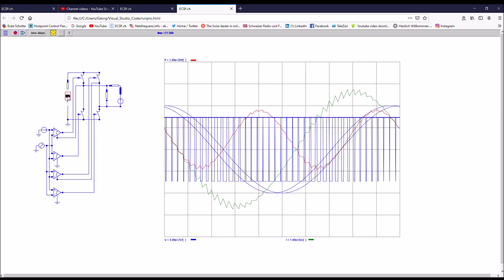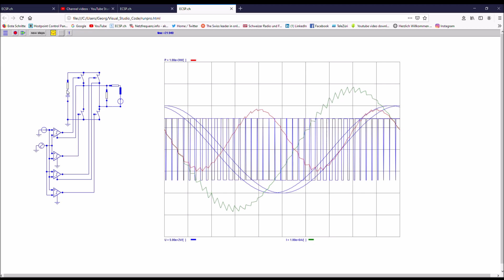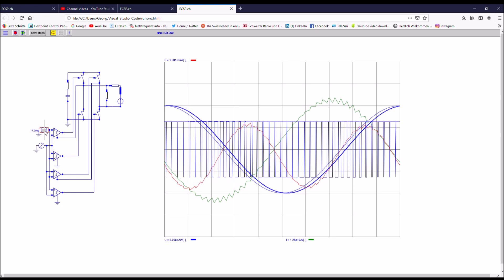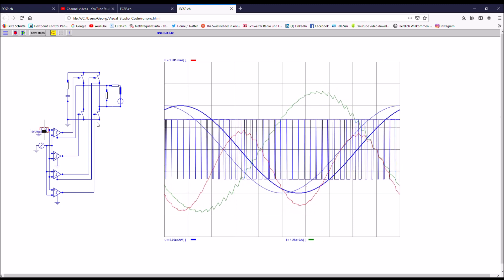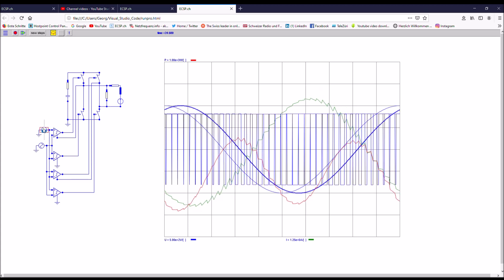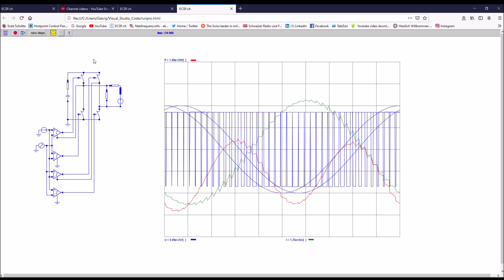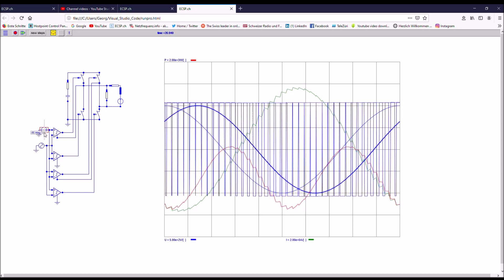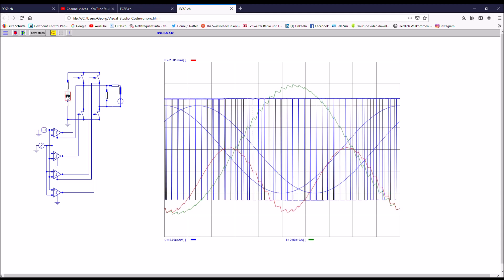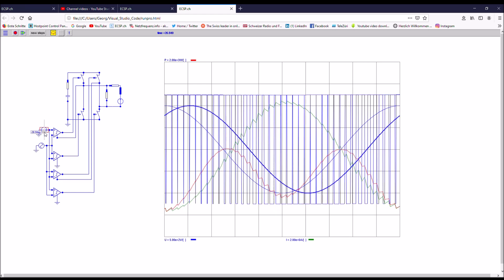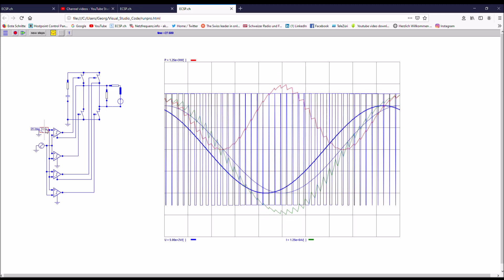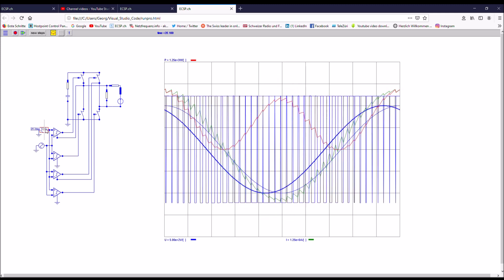You can see the converter output is now lagging — the load is leading the converter — and the voltage at the capacitor is decreasing. That means power flows from the DC side to the load side, causing the DC voltage to decrease. The other way around, when I move to a leading converter angle, the load side is leading the converter and power is now fed from the load side back to the DC side. This is how I control the power flow — with a leading load you can see the capacitor voltage increasing, and with the converter leading, the DC voltage decreases.